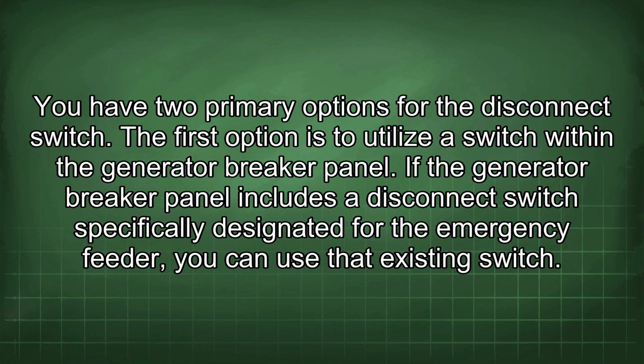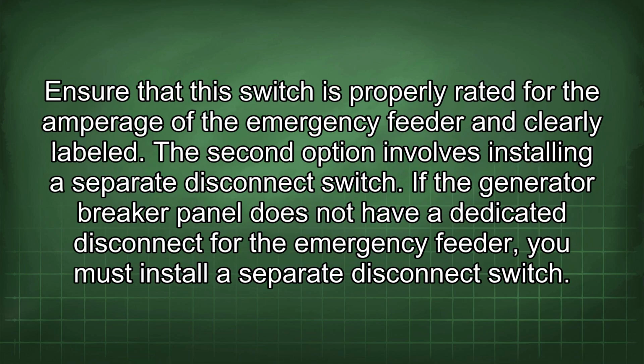First option is to utilize a switch within the generator breaker panel. If the generator breaker panel includes a disconnect switch specifically designated for the emergency feeder, you can use that existing switch. Ensure that this switch is properly rated for the amperage of the emergency feeder and clearly labeled.